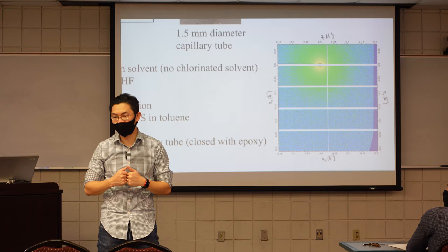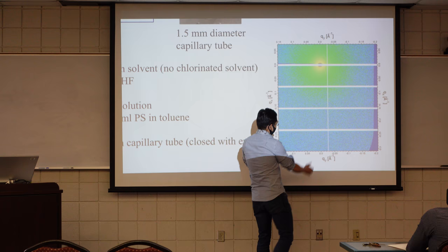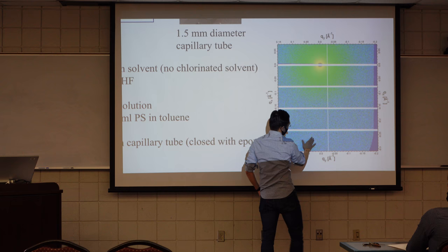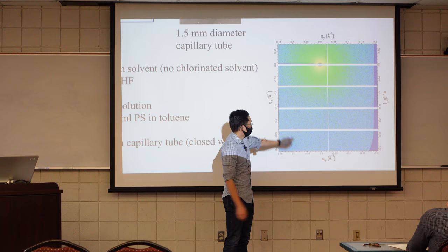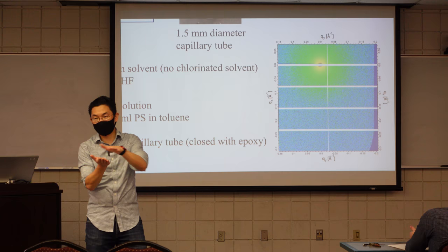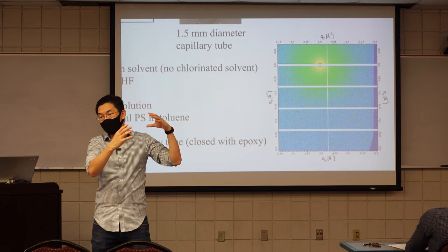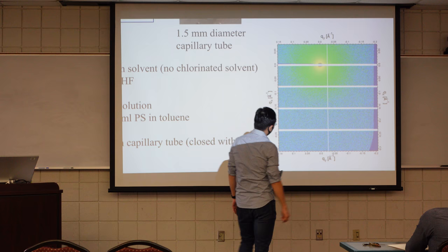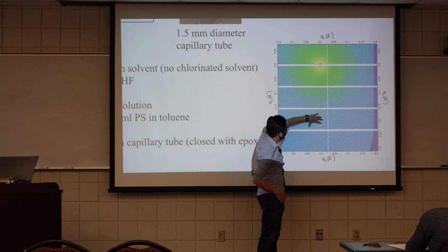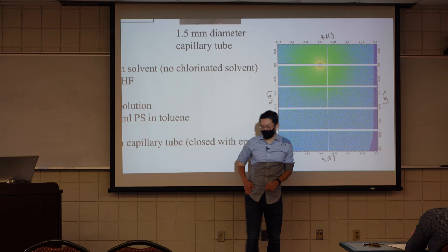So the 300K is made by the same thing, but instead of using this geometry, they just pick either this or they can actually align in this way, make it longer but narrower. The gap is still going to be there. There is no way you can eliminate it, just how they pack the modules. But the simple way our instrument can do is to shift the detector without shifting anything else. You just move the detector offset by angle. So you can image these areas and then you just need to stitch two sample detector images together, okay? However, even if you shift it, there's still a tiny area going to be overlapped. Think about you shift everything here. There's always a tiny bit of dead zone left, but the majority is gone.